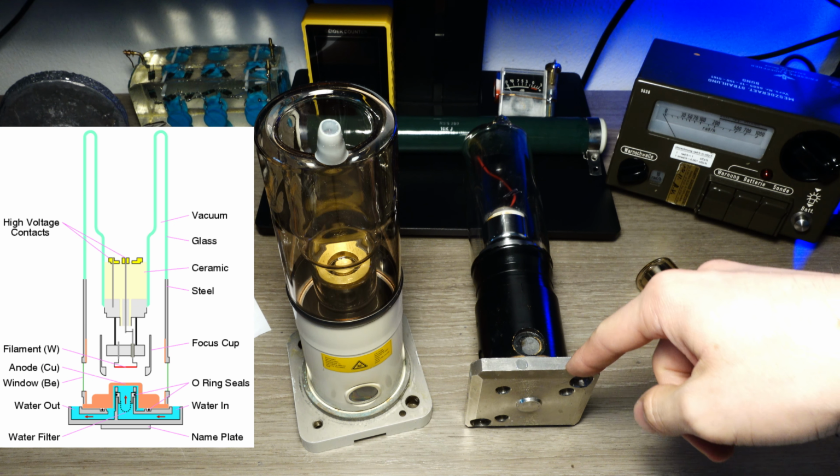And so they use a specific metal as the target, and the voltage is always lower than 60 kilovolts, due to the fact that you want to excite the metal of the target with the closest energy to the Bremsstrahlung spectrum that is superimposed over the characteristic X-ray emission of the metal, so that you have the highest number of X-ray photons at the specific energy that you want.